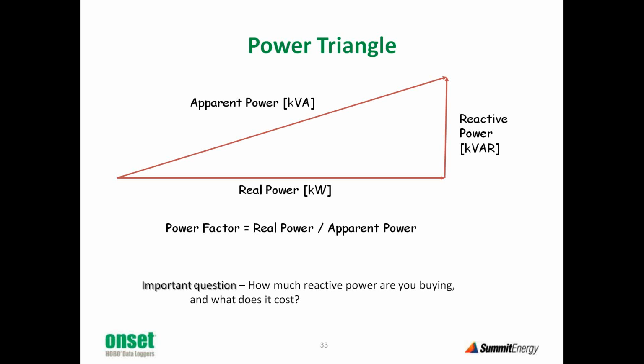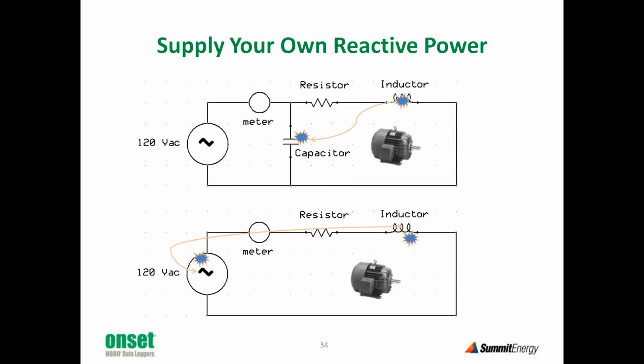So, important question, how much reactive power are you buying from your utility? Because remember, if you envision first in the lower diagram here, if the reactive power is bouncing between the inductor and the utility and back, if you're asking them to hold it for you on those other half cycles, it's passing through the revenue meter, they may be charging you for that. Maybe not. It's like demand charge. Everybody's different. You have to look at your electric bill, call your utility, ask them to explain it to you. Maybe, even though they're holding that reactive power for you on the half cycle, there's no charge for it. Or maybe it's a very small charge. But maybe it's a really big charge.